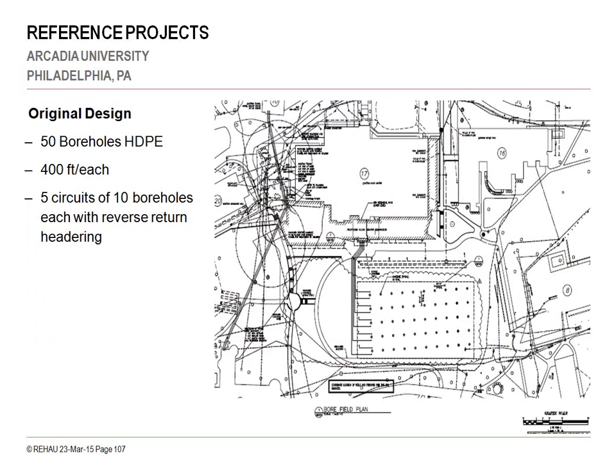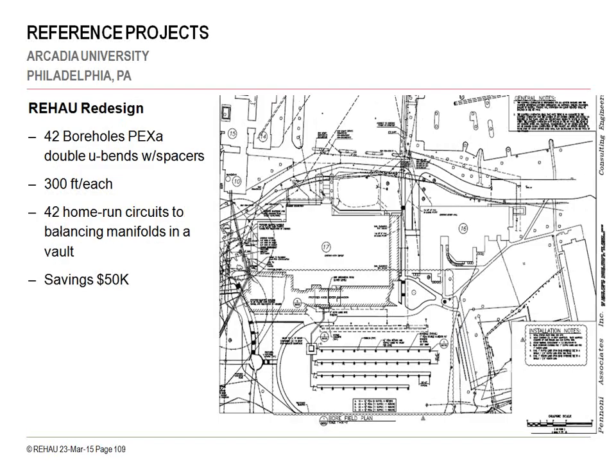RAUGEO was in touch with the general contractor before it got awarded out to the subcontractor driller and asked if they'd be interested in a proposal with the RAUGEO U-bend PEX-A materials that could reduce the size of the borehole field and potentially save money on the project. This is the redesign. We did size it down to 42 boreholes from 50 boreholes originally, and instead of 400 feet, 300 feet. And so what we have here are 42 boreholes where we are using those 2 branch tees of each borehole, and we're having 1 and 1/4 inch supply and return from each borehole.